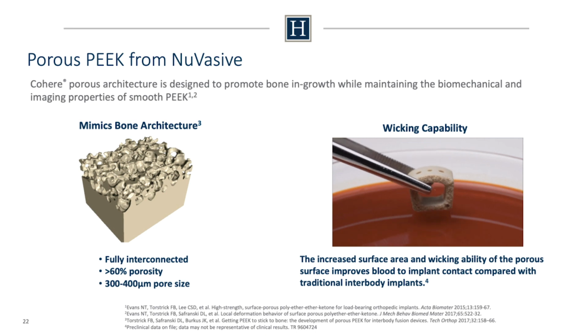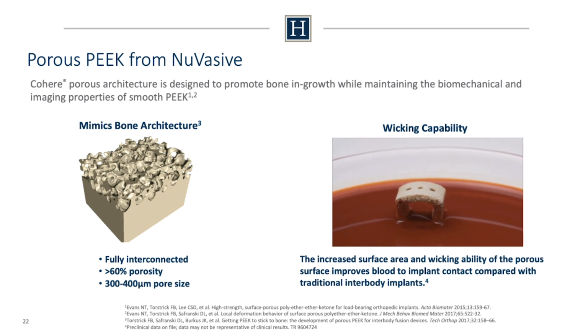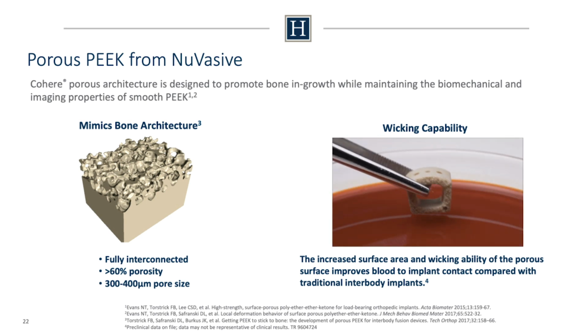With these lessons in mind, NuVasive has re-engineered the surface architecture of PEEK implants and is the only company to offer Porous PEEK technology for spinal fusion procedures. Porous PEEK, under the brand Cohere, features an architecture designed to promote bone ingrowth while maintaining biomechanical and imaging properties of PEEK. The surface mimics bone with its highly porous interconnected architecture.